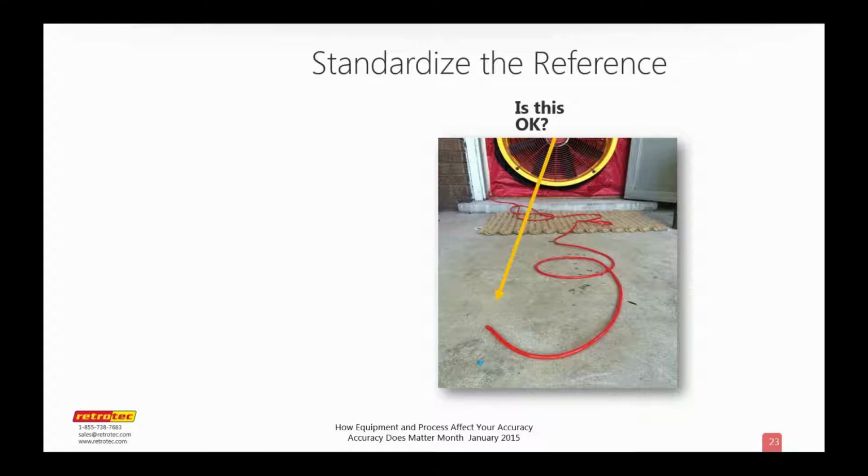And we've started to realize, we constantly heard, oh, their fan's not calibrated. When was the last time they sent it in for calibration? When was the last time that they checked it? We would check these fans and find out it wasn't the fan. What we started to find out was that it had a lot to do with 3 things. One, where their reference hose was.